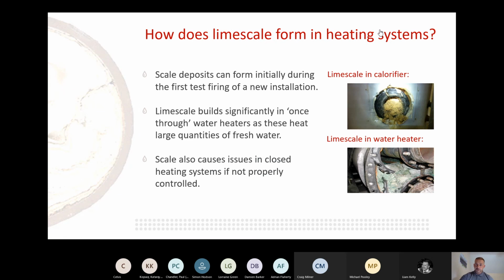So how does scale form in heating systems? Scale deposits, as it says there, can form from the initial firing of any system. High heat flux and low water volumes exaggerate the precipitation of calcium, and the image there shows that, obviously, to the extreme. That's a mud flap or an inspection hole on a calorifier.